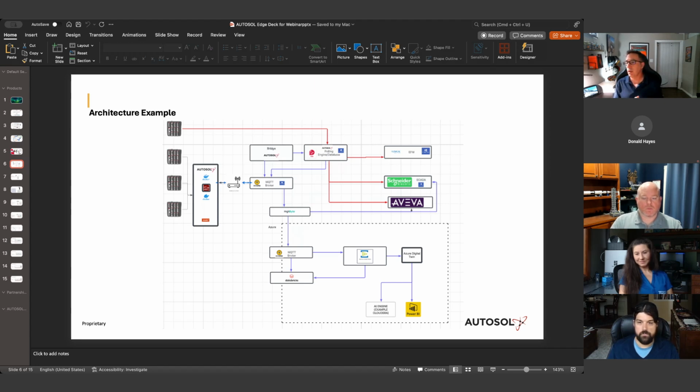whatever resolution they want. And one of the advantages of doing it this way when you deploy your edge program is to get all those people in the room, because instead of them talking to an independent device, 4 or 5 things talking to one device, use MQTT, use AUTOSOL and such to talk to the device once, bring that data in, and then your SCADA, your measurement folks, your historian folks, and those other tools that you use can share in that same data.